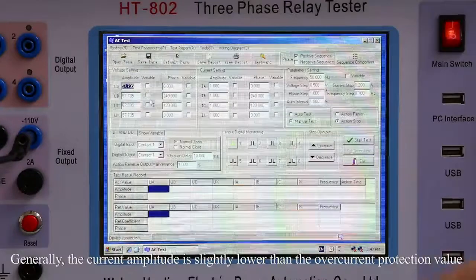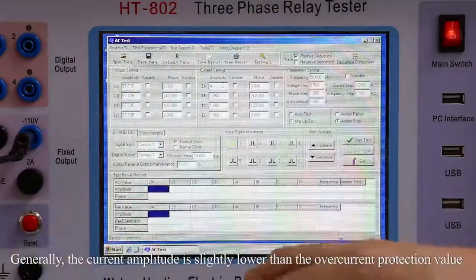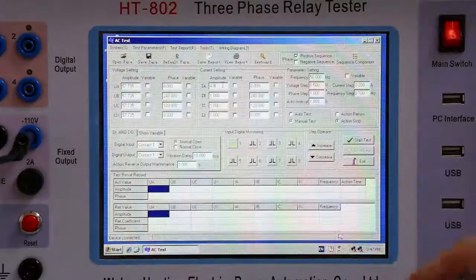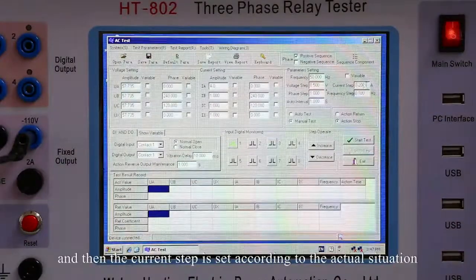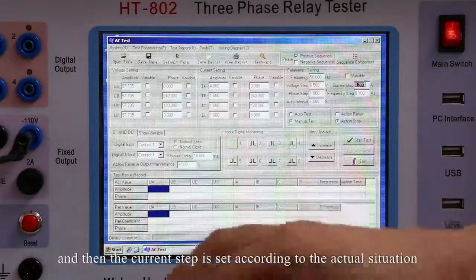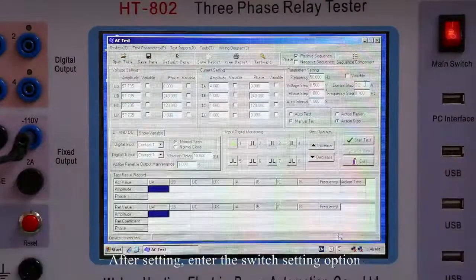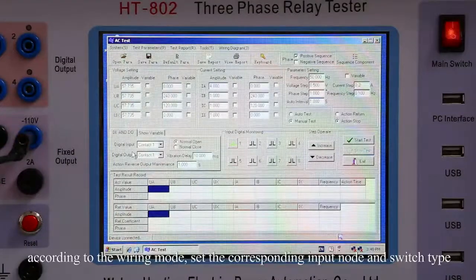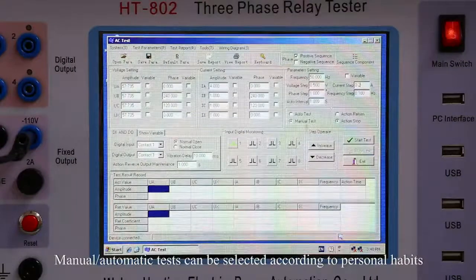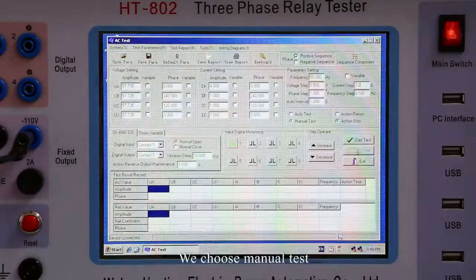Generally, the current amplitude is slightly lower than the overcurrent protection value. And then the current step is set according to the actual situation. After setting, enter the switch setting option. According to the wiring mode, set the corresponding input mode and switch type. Manual or automatic tests can be selected according to personal habits. We choose the manual test.